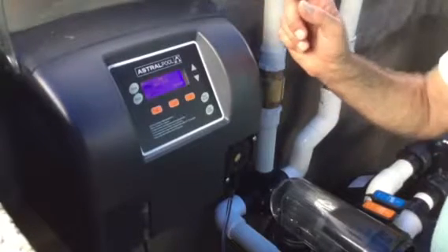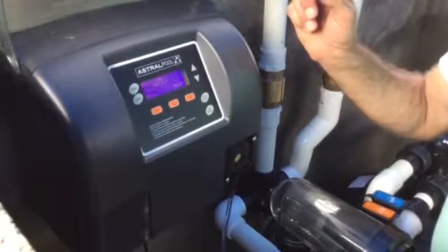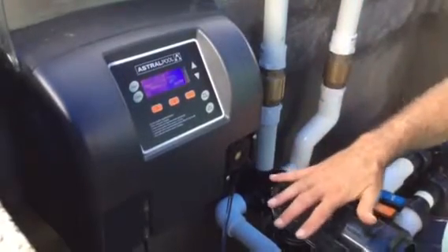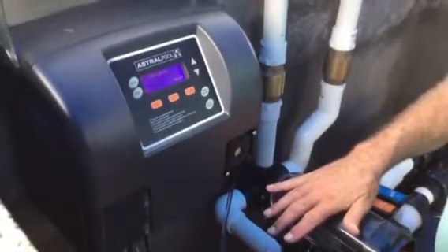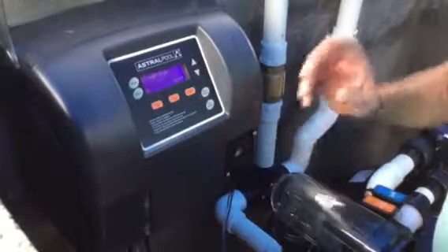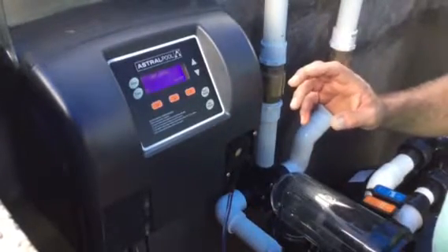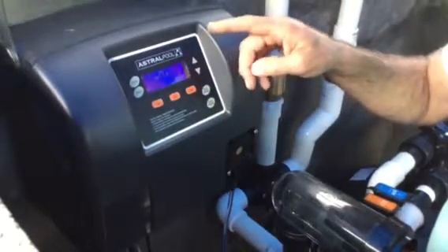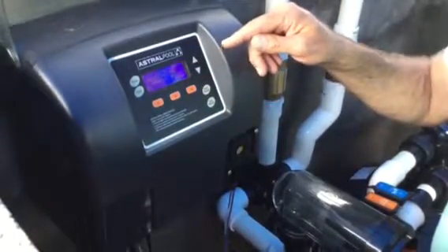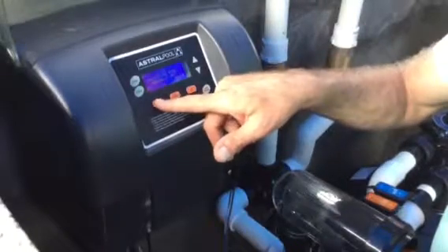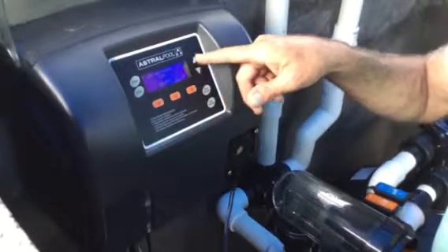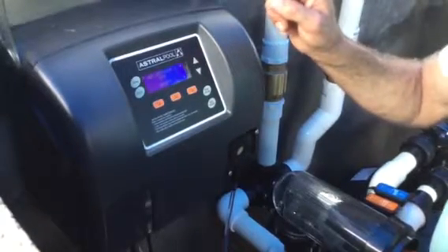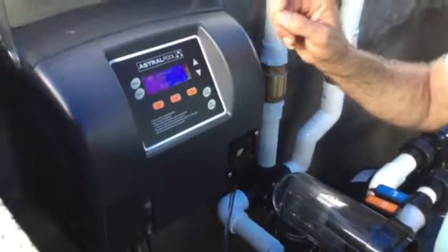And so if we're checking, because during the day at this stage we're running this, so this will be generating chlorine during the day. And so at the end of the day we want it to be 3. So once again, if our chlorine reading we're taking at the end of the day is too low, press set, increase the set point by 20. If our chlorine level is higher than 3, decrease it by 20.